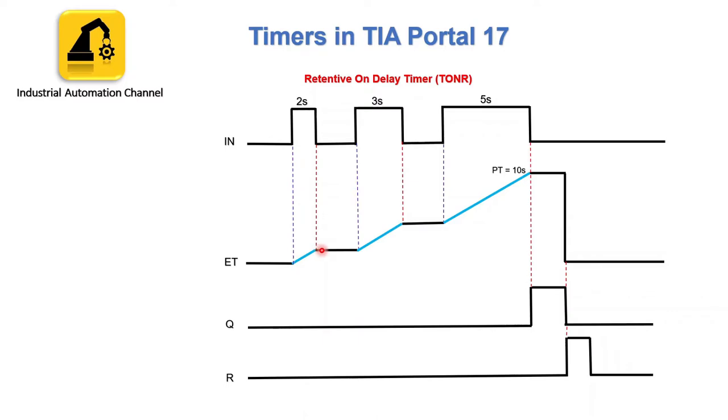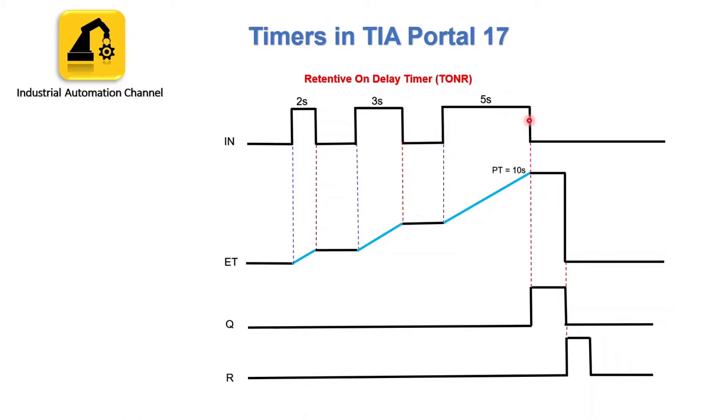It's unlike the TON. Again when the input is on, the timer starts to count and resumes from 2 seconds. After 3 seconds the input is again off and elapsed time is 5 and it will remain at this time. The third time input is on and after 5 seconds is off. The preset time is completed now and the output will be on. If we give a signal to reset and activate this input, elapsed time will be 0 and output will be turned off.